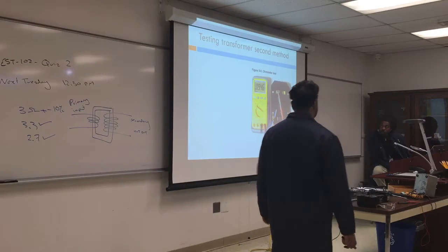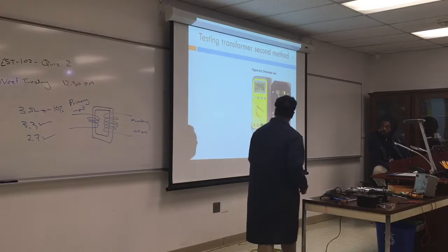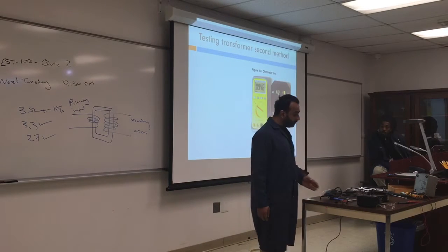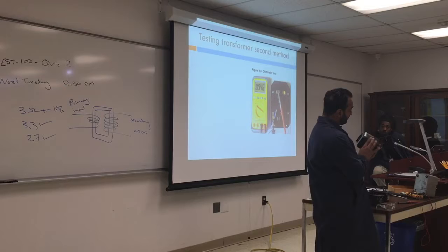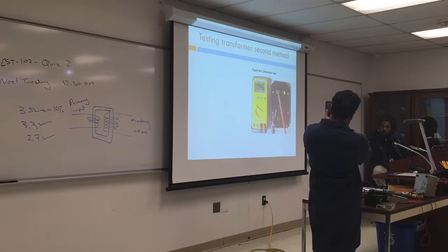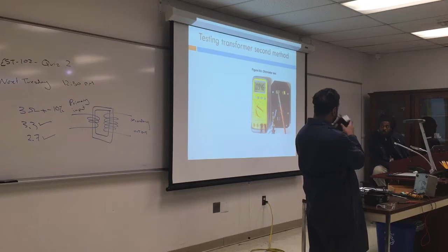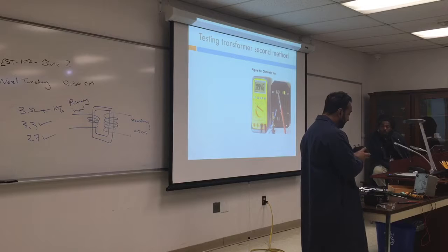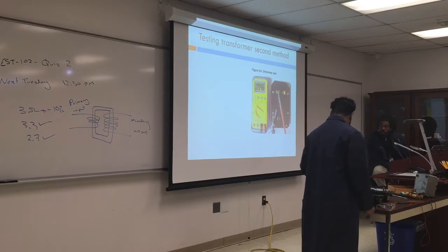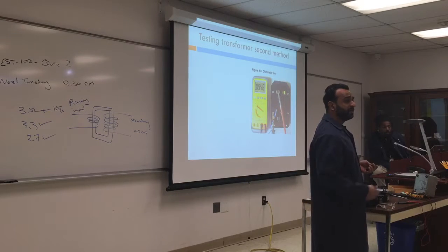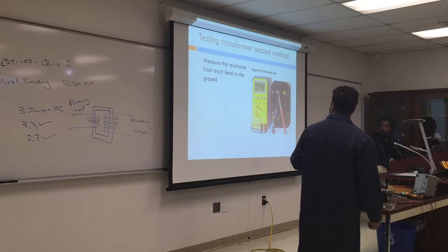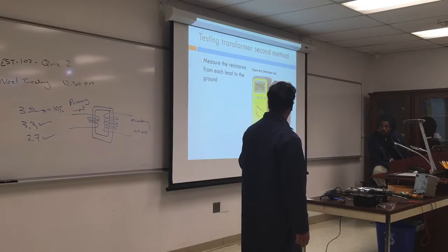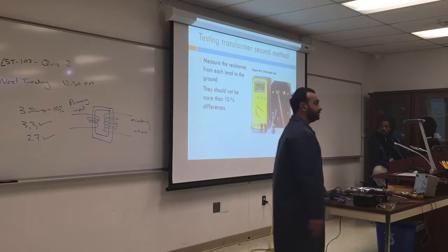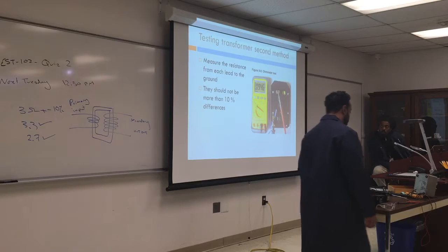This is another, second method, just testing the transformer without powering it up. If you look at the transformer, it has a ground in it. And if you look here, it will tell you what resistance to expect and how to test the ground. So again, we're testing for resistance because we're thinking about the wire inside. Measure the resistance from each lead to the ground, and they should be within 10% of each other. So let me do that.